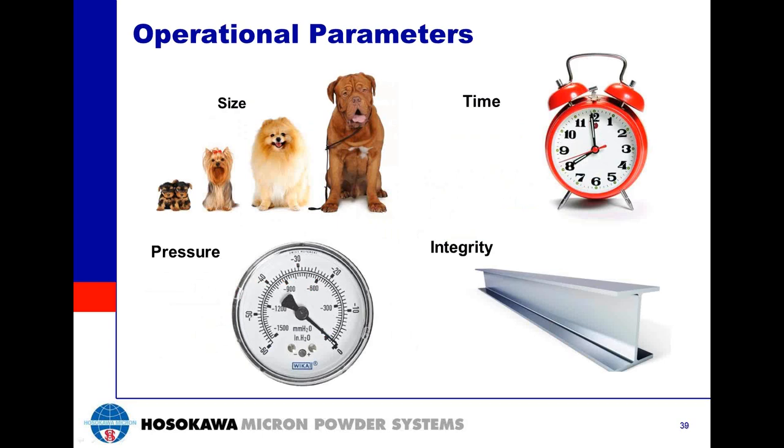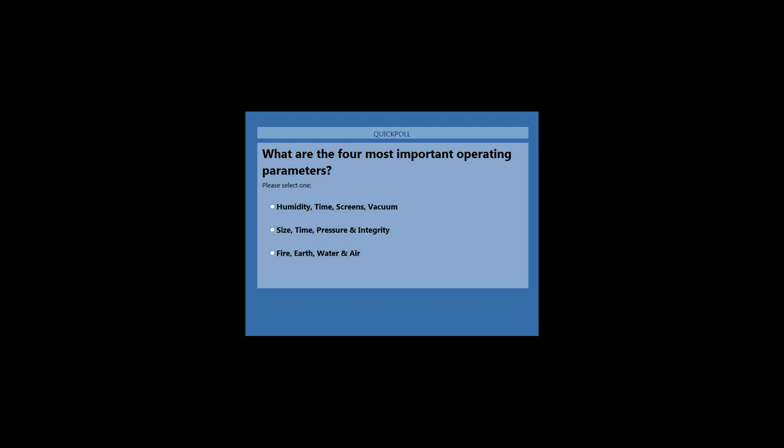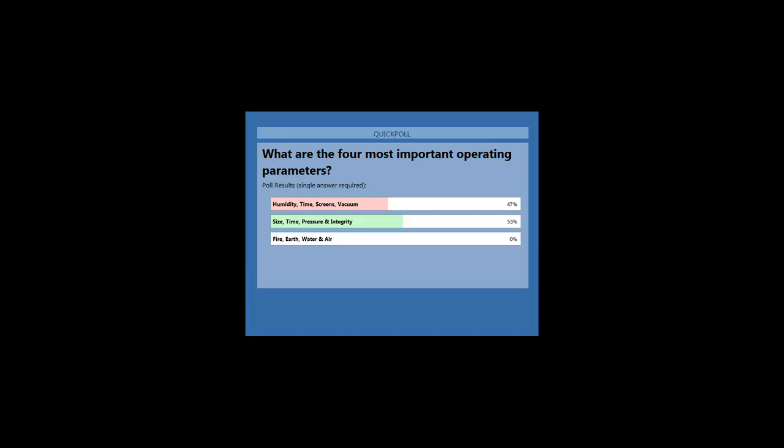Our third poll question: what are the four most important operating parameters? The choices are humidity, time, screens, and vacuum; or size, time, pressure, and integrity. The poll results show 47% said humidity, time, screens, and vacuum, while 53% said size, time, pressure, and integrity. Those who answered humidity, time, screens, and vacuum were very close, but the correct answer is size, time, pressure, and integrity. Humidity plays an important part, but it is not one of the four operational parameters in pneumatic sieving.